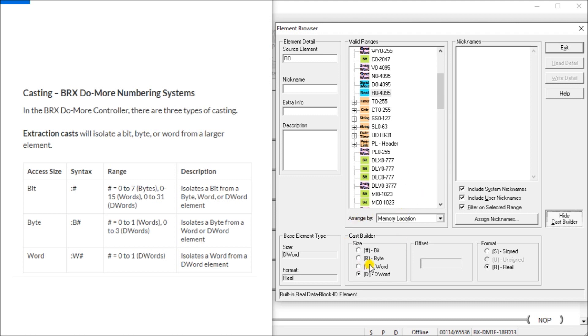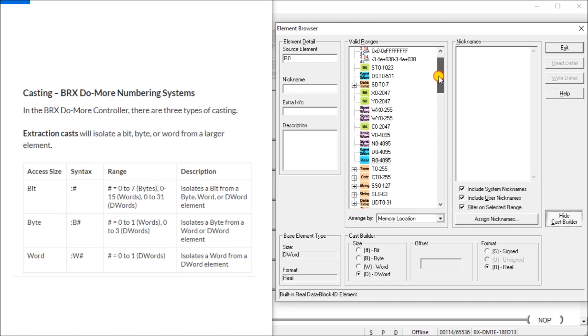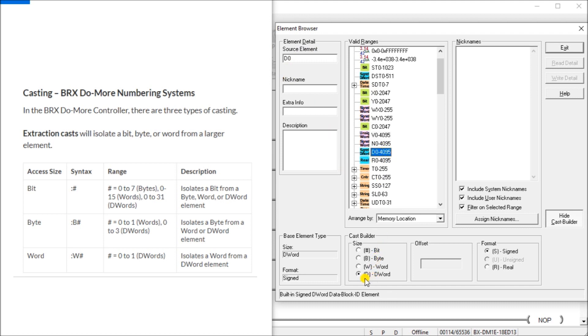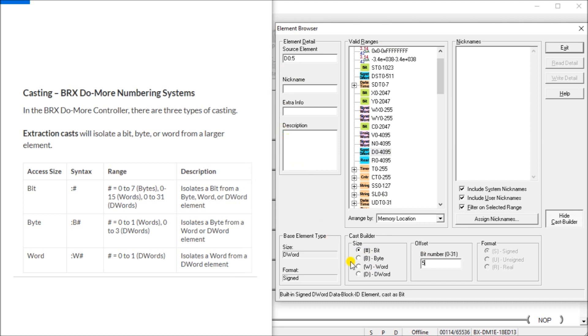So the first one, and you can see it right here. So if we were to look at, let's say a V memory. And we want to look at the bit. So one bit of that, we can specify which bit number we want here. And you will see now our element comes up as V0 colon three, which means bit number three of V0 word. That can also go for a double. And we can look at the bit of a double word. Again, if we go five, you'll see that D0 5.